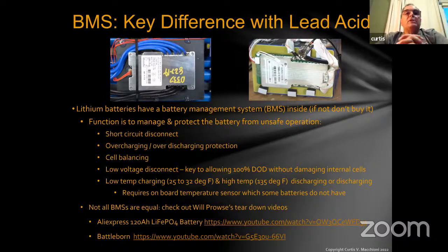The battery management system is also there to protect against charging at too low of a temperature, which is definitely something you should not do with lithium batteries. The spec on these ranges from 32 degrees Fahrenheit, or freezing - some go down to 25 degrees - and then there's a high temperature spec of 135 degrees. Hopefully we're not in environments of 135 degrees and worrying about charging or discharging in those temperatures.